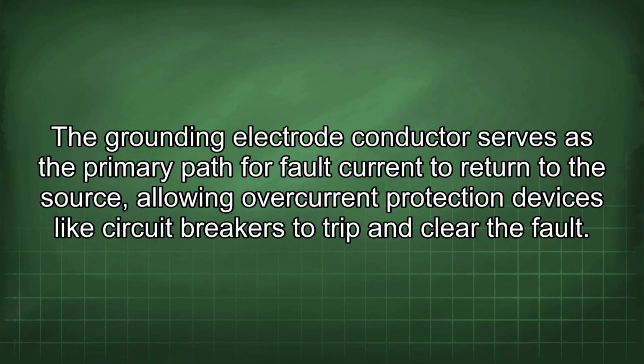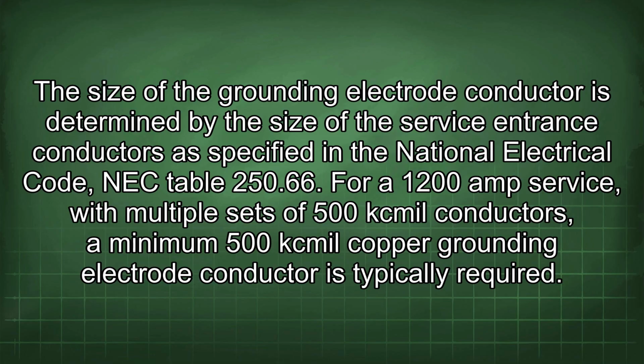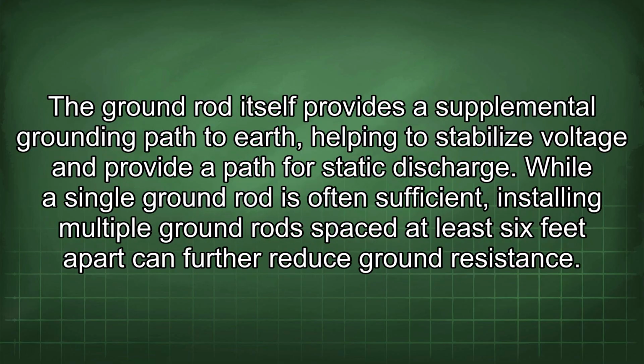The grounding electrode conductor serves as the primary path for fault current to return to the source, allowing overcurrent protection devices like circuit breakers to trip and clear the fault. The size of the grounding electrode conductor is determined by the size of the service entrance conductors as specified in the National Electrical Code, NEC Table 250.66. For a 1200 amp service, with multiple sets of 500 kcmil conductors, a minimum 500 kcmil copper grounding electrode conductor is typically required. The ground rod itself provides a supplemental grounding path to earth, helping to stabilize voltage and provide a path for static discharge.